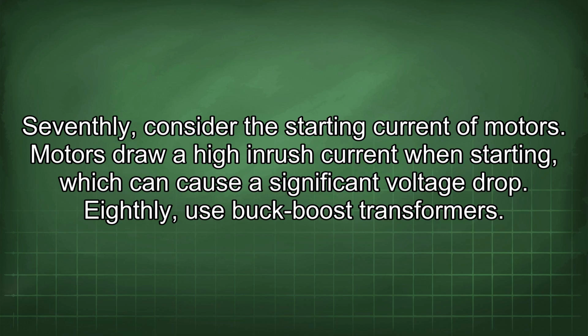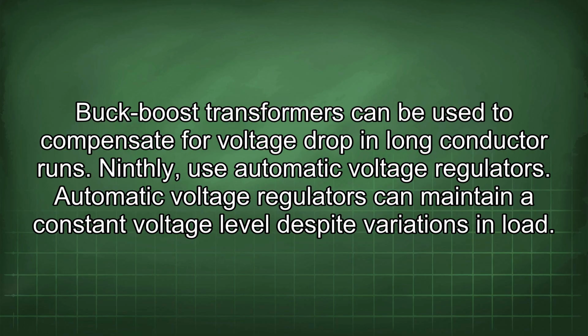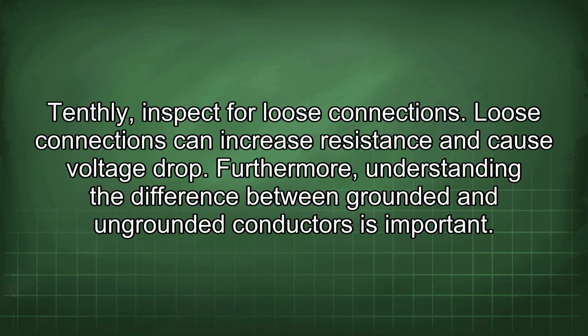Eighthly, use buck-boost transformers. Buck-boost transformers can be used to compensate for voltage drop in long conductor runs. Ninthly, use automatic voltage regulators. Automatic voltage regulators can maintain a constant voltage level despite variations in load. Tenthly, inspect for loose connections. Loose connections can increase resistance and cause voltage drop.